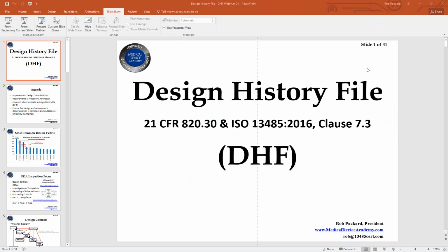and your DMR. So what I typically have is I have a technical file index and a DMR index, and they serve one and the same, and I might have more information in my DMR than you normally need as a minimum, but it sometimes eliminates people needing to go dig into my DHF because often they're looking for the most recent change.